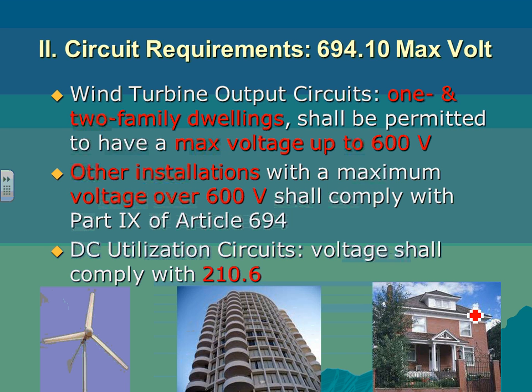You can get 13,800 volt. I don't see them making it at this level. If you're doing dwelling, you're limited to a maximum voltage of 600 volt or less. That's typical also on the solar. You're limited to 600 volt or less. Other installation, if you're doing wind on non-dwelling premises, there's no limitation on the voltage.